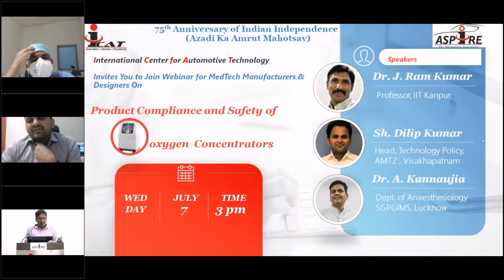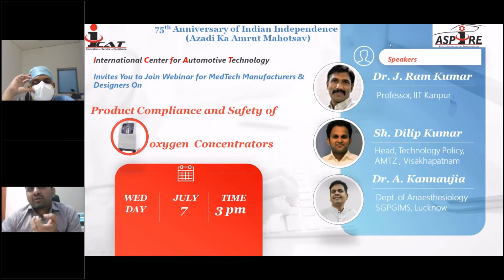So zeolite is actually an extract from lithium or the sodium one. So it totally depends upon the quality, because it actually determines the purity. If, for example, there are suppliers like Honeywell and one Chinese company who supply the zeolite, the quality of each of them is totally different. If 1 kg of Honeywell zeolite is used, it caters as per the specification, which is 93% plus or minus 3. But with the Chinese one, if they want to meet 93 purity, they at least need 1.5 kg of zeolite.